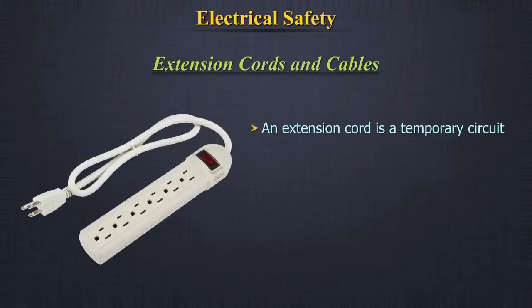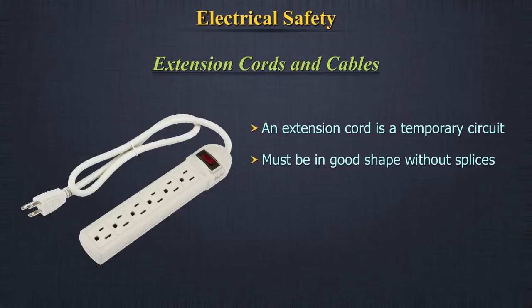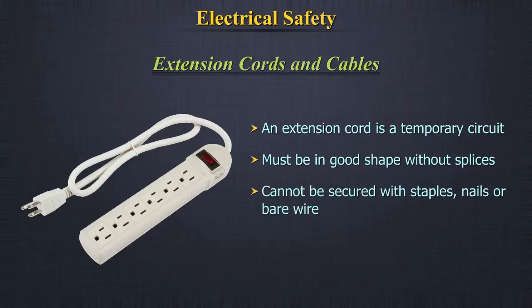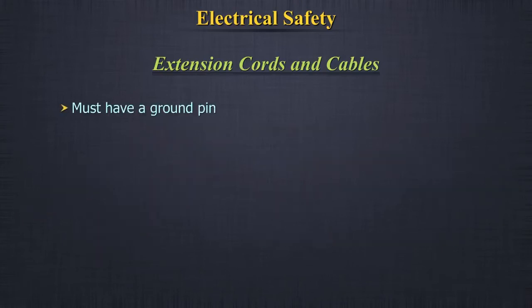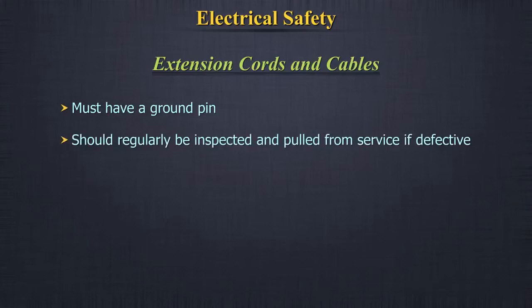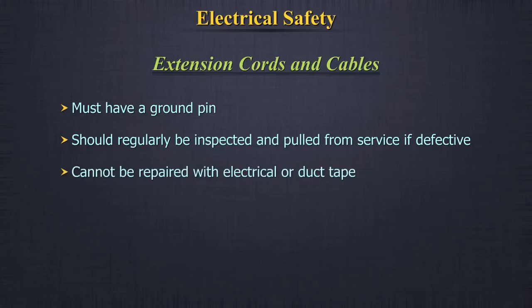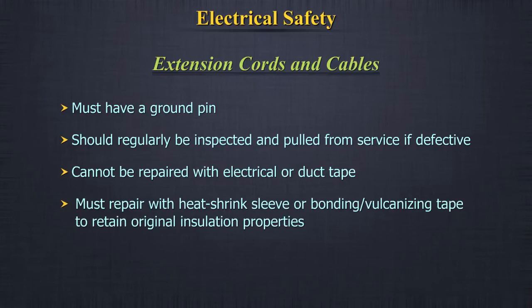An extension cord is a temporary circuit. It must be in good shape without splices. It can't be secured with staples, nails, or bare wire. It must be protected from damage. They must have a ground pin. They should regularly be inspected and pulled from service if defective. Cannot be repaired with electrical or duct tape. Must repair with heat shrink sleeve or bonding vulcanizing tape to retain original insulation properties.